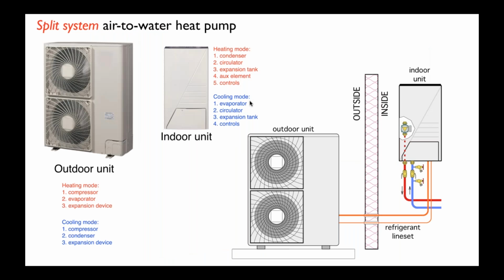Okay, now the other common configuration is what's called a split system. Now we have an outdoor unit and an indoor unit, and we're connecting them with refrigeration piping, refrigeration line sets. Residential 4 or 5 ton unit, usually it'll be like a 5/8 or 3/4 inch suction line, and then the liquid line is going to be a 3/8 line. So what are the advantages and disadvantages?